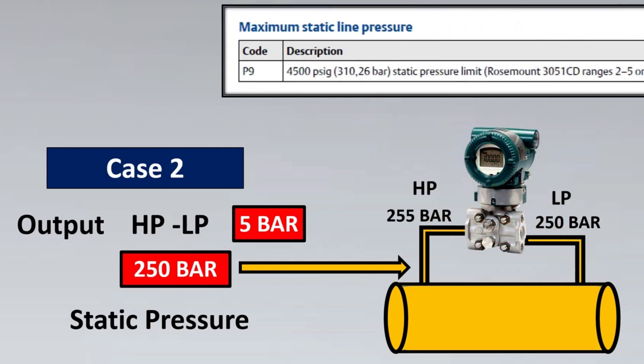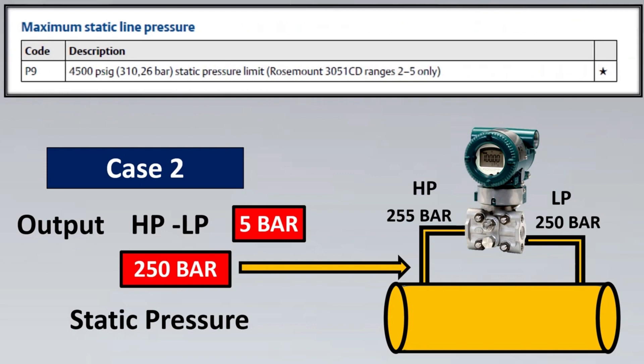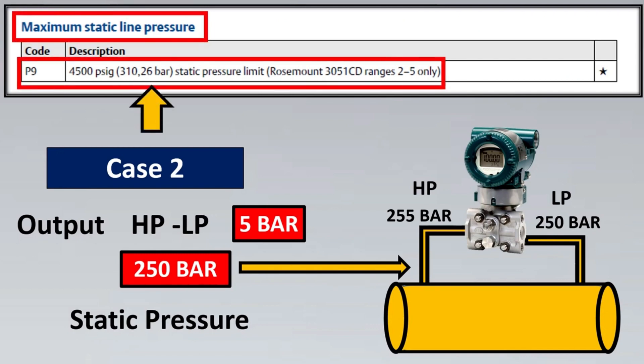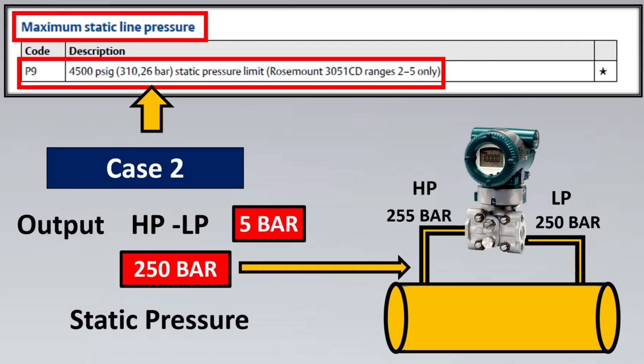Don't worry — there is a solution. In that same catalog, there is a special code, P9. With this code, the maximum static inline pressure goes up to 310 bar. Since our static pressure was 250 bar, we can specify code P9 in our requisition or data sheets and safely use this transmitter. This mistake is made by many engineers, and site queries about transmitter failures often trace back to this — so please be conscious about it.